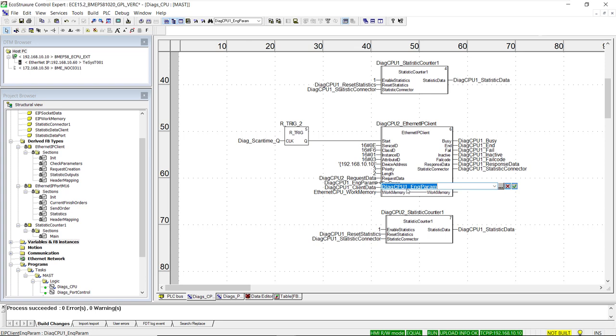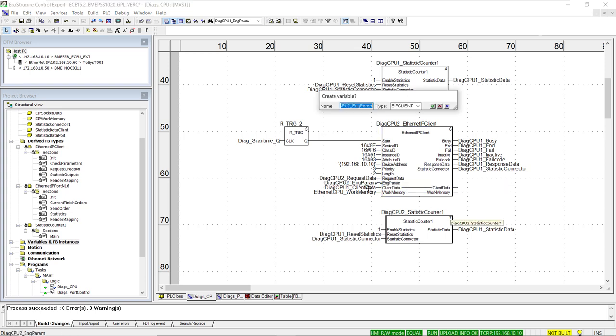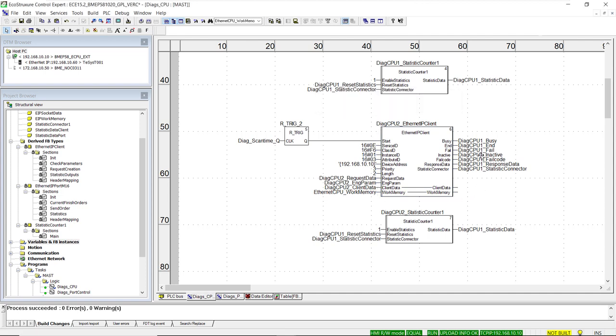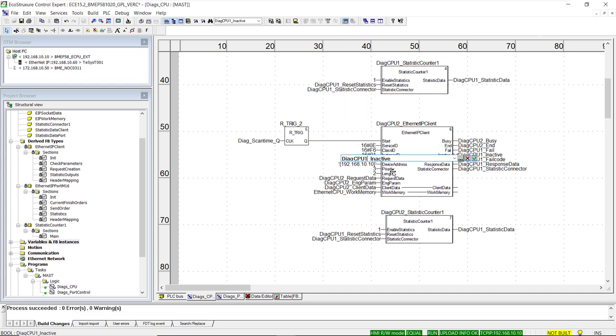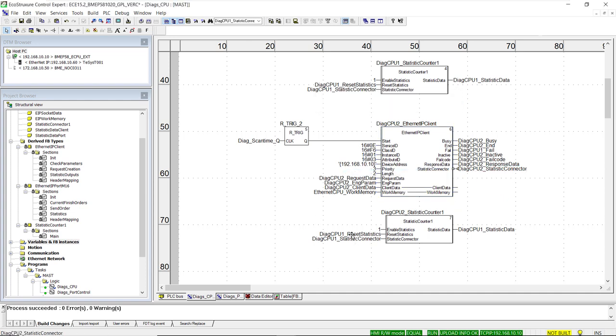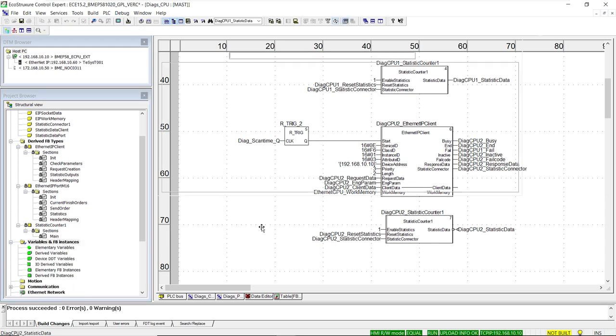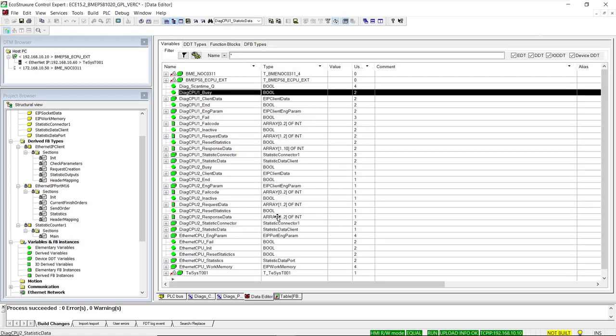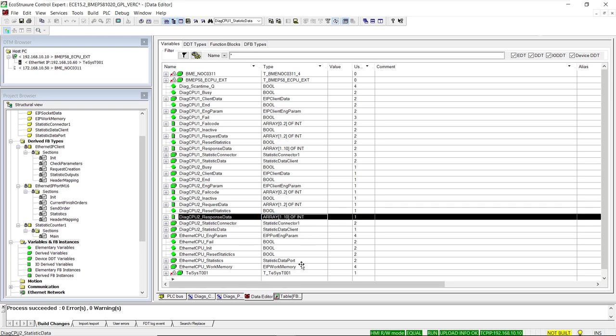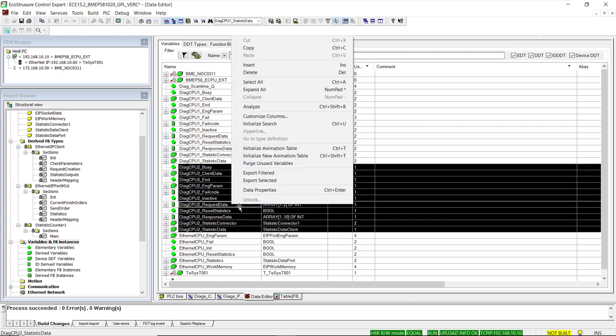This naming approach provides a consistent convention for each structure. The work memory input variable at the bottom left remains the same, since this new Ethernet IP client function block is connected to the same port function block already configured. We continue renaming variables on the outputs of the new client function block and the associated statistic counter. When using copy-paste, remember that the response data array may not be automatically sized large enough for the expected data, so always adjust it.